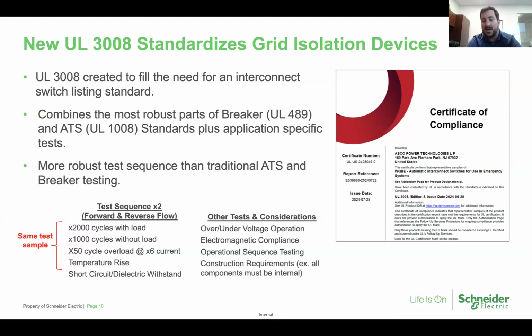This standard actually combines aspects of UL 1008 from a transfer switching point of view with generators, as well as UL 489, which is the molded case circuit breaker standard, because isolation is really a single contactor device. You don't need two sets of contactors. It took inspiration in parts from both of these in terms of construction requirements, functionality and sequence of operation requirements, to create this new standard and the new need for this interconnect, which is slightly different than both of those, just drew inspiration from it.